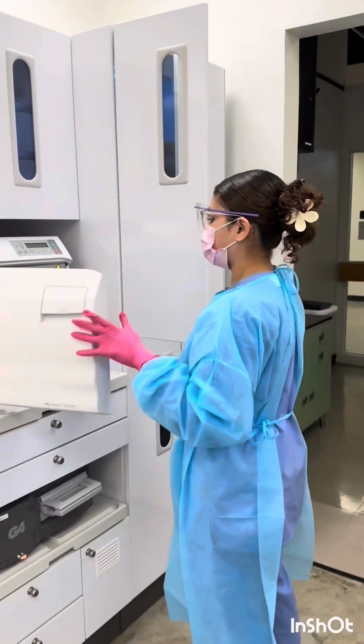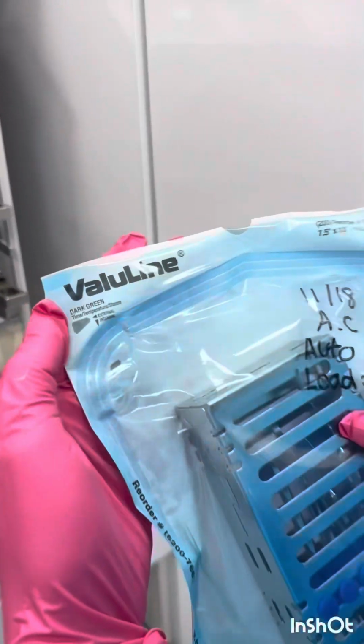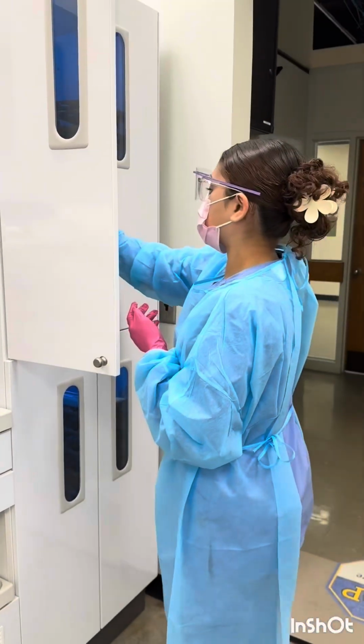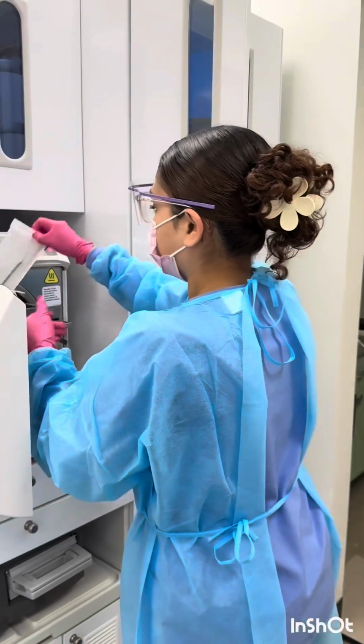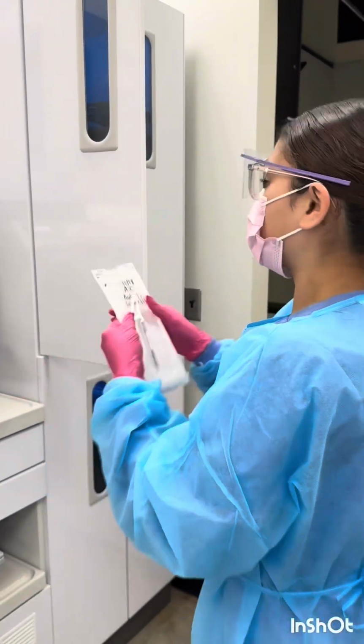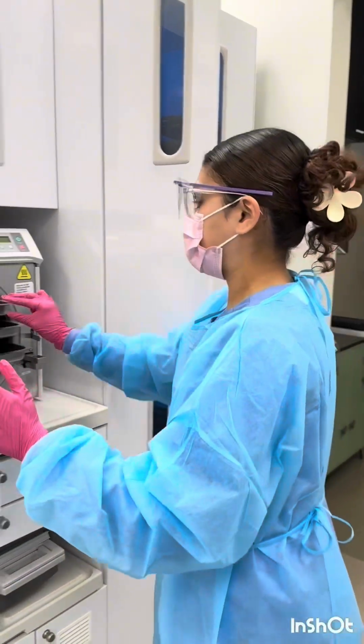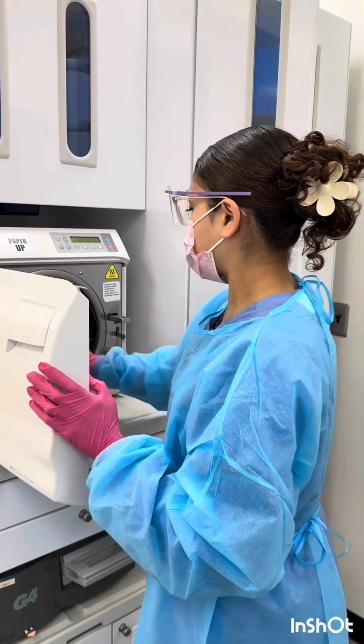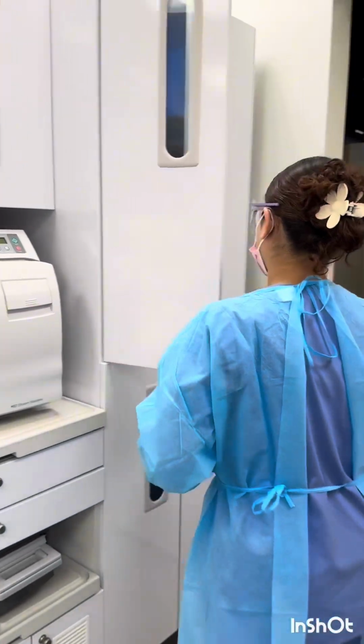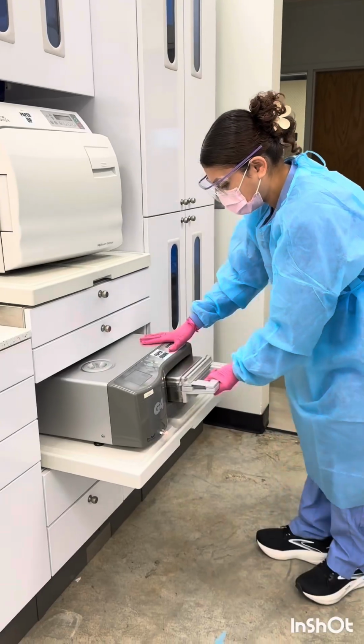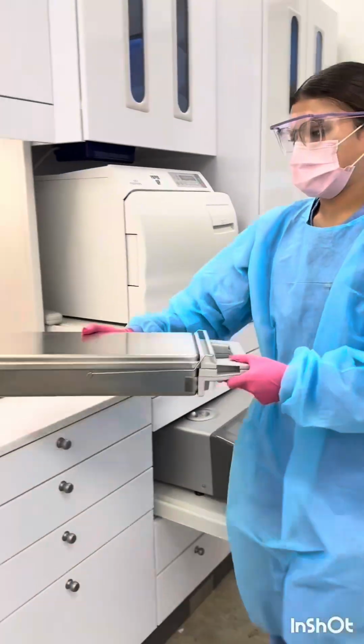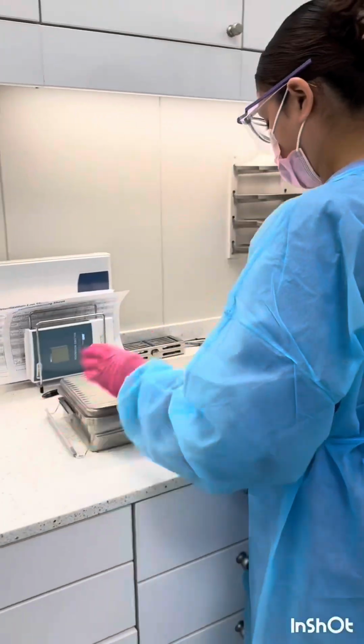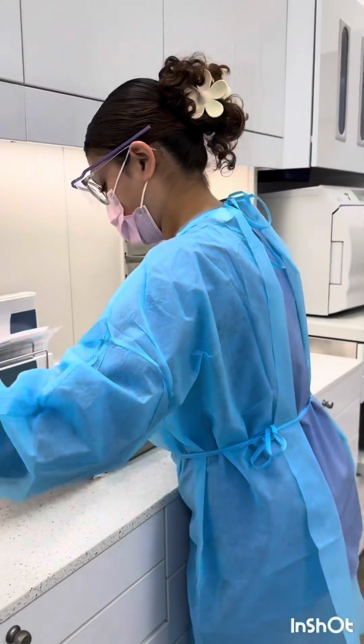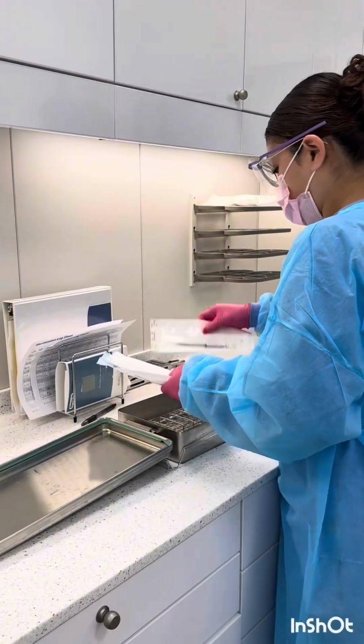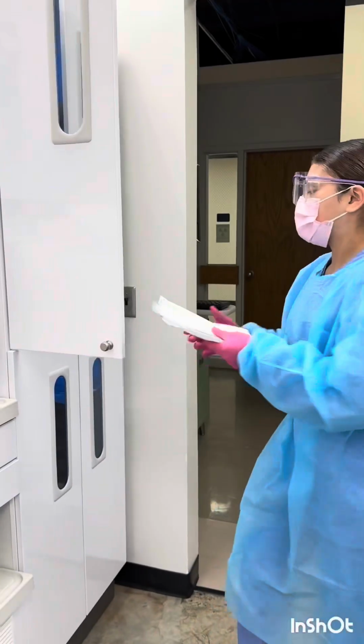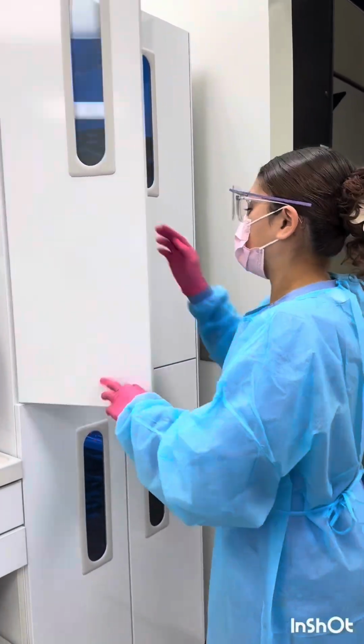The autoclave is fully done sterilizing and drying. Make sure the pouches are fully dry before placing them in the blue zone. Make sure the indicators on the pouches have changed colors, indicating they are now sterile. We'll do the same thing with the Statim, also making sure they are fully dried to prevent wicking and making sure that the color indicator has changed, indicating that they are sterile. The Statim has a USB chip that records when it was run, so there's no need to record.